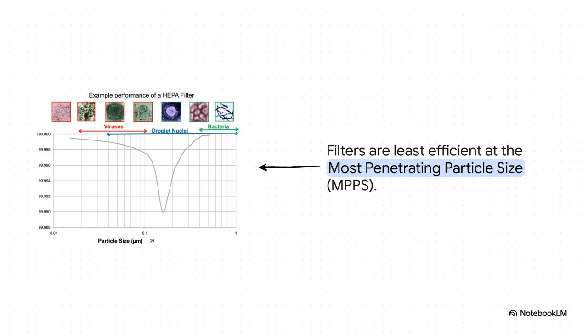Now this is where the science gets really interesting and kind of weird. You'd automatically think that the smaller a particle is, the harder it is to catch, right? Well, not quite. Really big particles just get stuck easily, and the teeniest particles are so light they basically bounce around like crazy until they eventually hit a filter fiber. But there's this weird middle ground, right around 0.3 microns. They call it the most penetrating particle size, where particles are too big to bounce around much, but too small to be easily caught. That's the filter's absolute weakest point. So by testing and certifying the filter at its worst possible performance, you guarantee it's even better at catching everything bigger and smaller. It's brilliant.